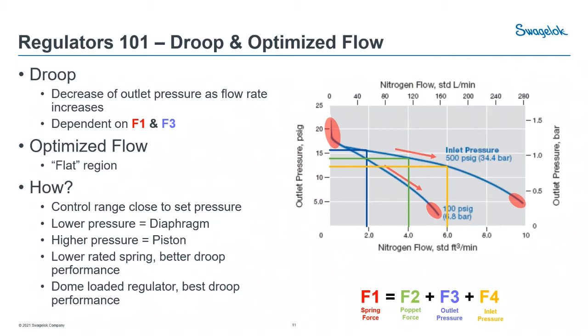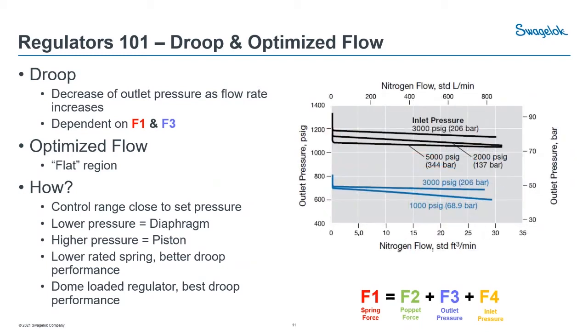How do we actually get into that flat range? When selecting a regulator, you really want to pick one that has a control range close to your set pressure. For lower pressures, use a diaphragm sensor instead of a piston. For higher pressures, use a piston sensing regulator. A lower rated spring will provide better droop performance, but dome-loaded regulators give the best droop performance — as you can see in this flow curve example, the lines are quite flat. This is what you'll tend to see a lot in the RHPS series, which also utilizes much larger pressures.